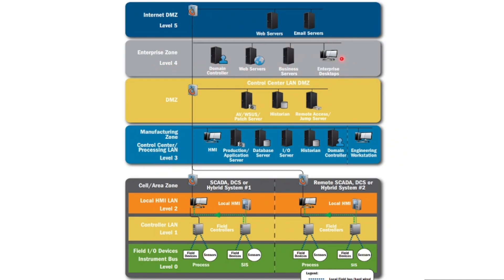We can map what type of servers to place in each level depending on the business use case. These levels are created because each level requires a similar set of cyber security controls. For an HMI zone or local HMI LAN, we can apply application allowlisting, IDS, and antivirus. For a field cabinet, we can do cabinet locking and physical access controls. For field-level devices, we do tagging, asset inventory, and asset management. For the enterprise zone, which is mostly IT-type systems, we can deploy EDR and UEBA.